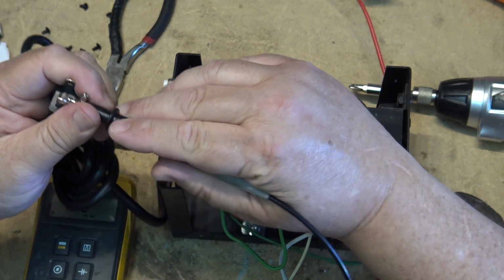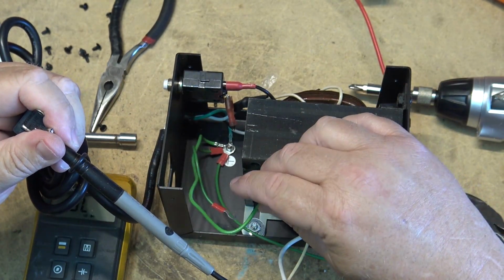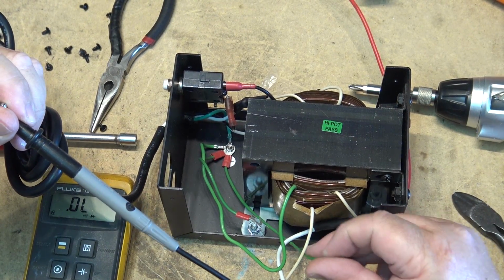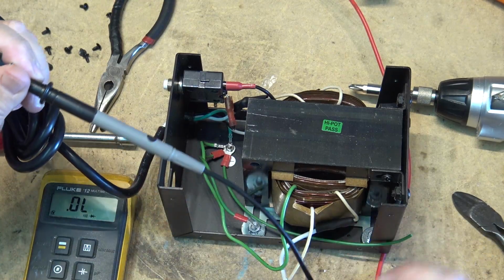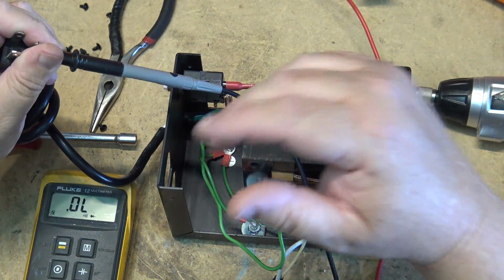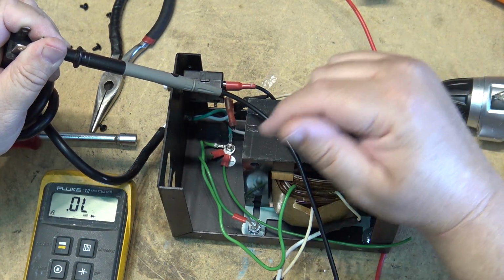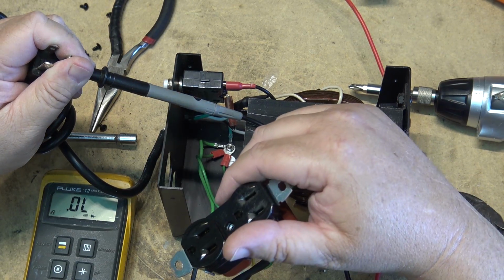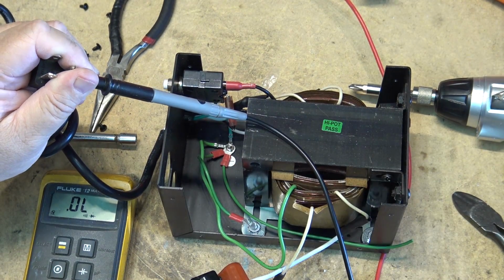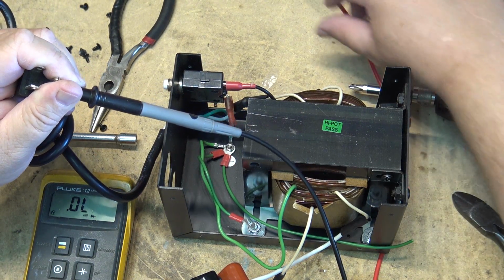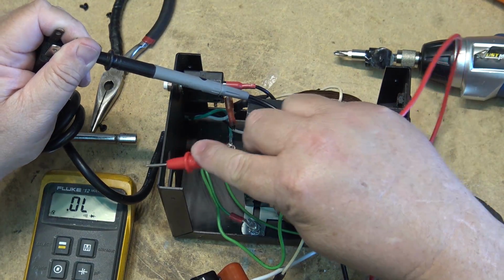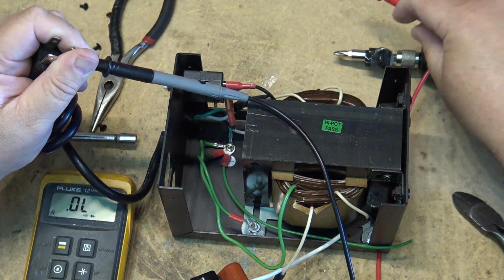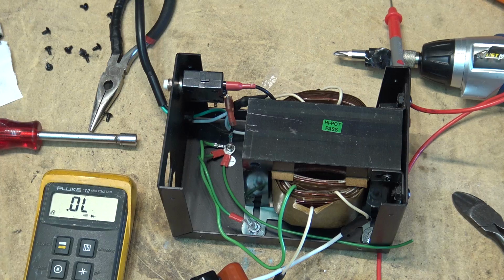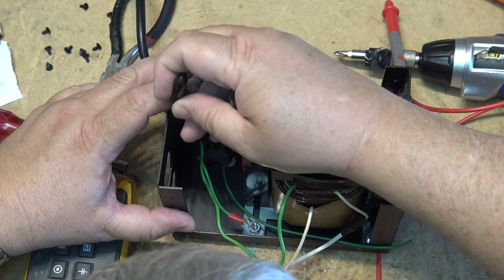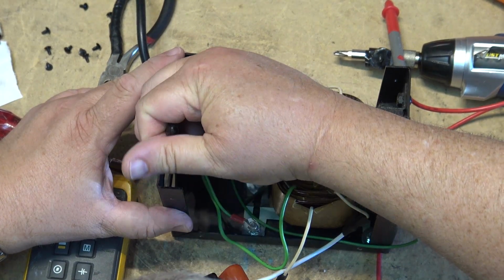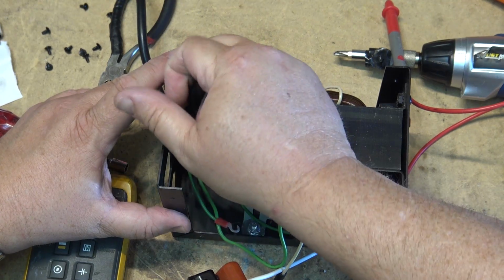Right now, by just removing the green wire that went to the neutral and the green wire that went to here, I've now isolated the actual plug from the supply. But as you can see, as soon as I connect the plug back up to here, I've kind of defeated the purpose. So I actually have to remove all the ground wires. We'll just do that right down here. We'll just take all the ground wires off as they're no longer needed.